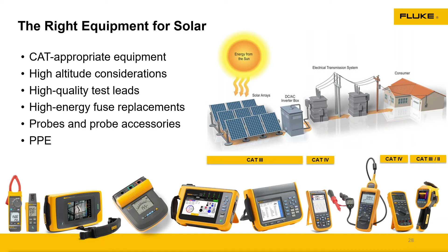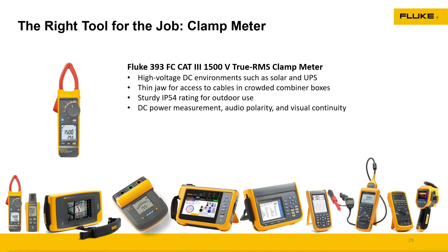As I mentioned through this whole aspect, having voltage and current measurements is huge. So have the right meter to be able to work with that. Whether it's a thin jaw capability, the IP54 rating is your environment. That is your ingress protection. That helps when it's raining or you have dust, so you know those particles won't get inside your meter to cause a problem. Having the right tool for that is going to be a big win. Also, an irradiance meter is going to allow you to validate what your sun output is.